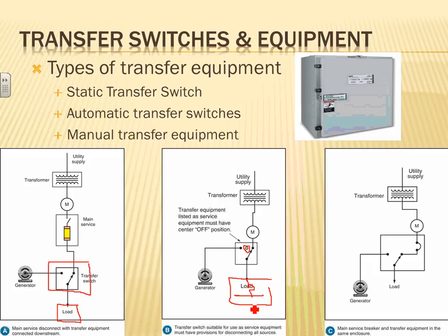Now, how would you qualify that one here? Is it an emergency generator when you back up the whole building? Legally required standby generator or not? So that's where this would be a good example. If you have a critical operation power system, that would be a good application where you back up the whole building through an auto transfer switch.